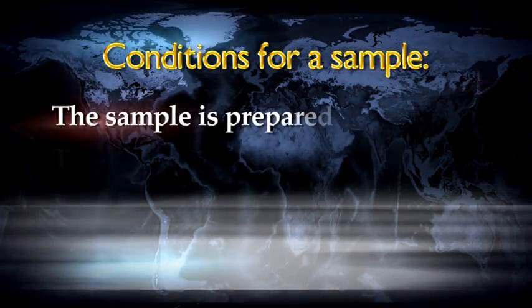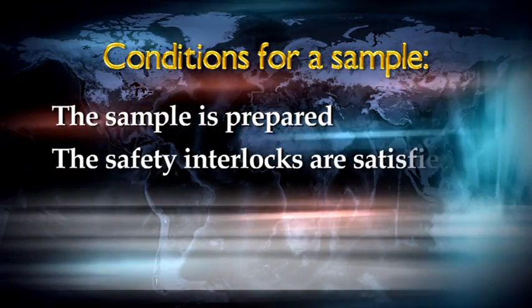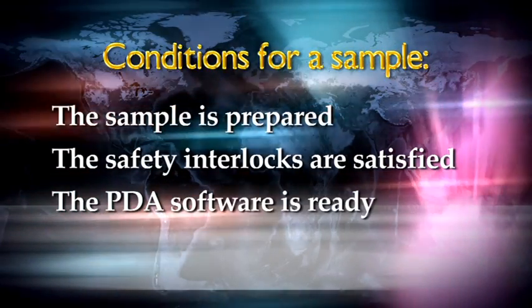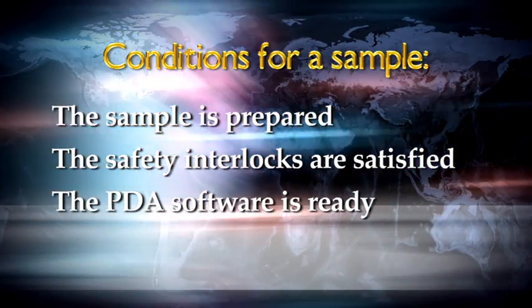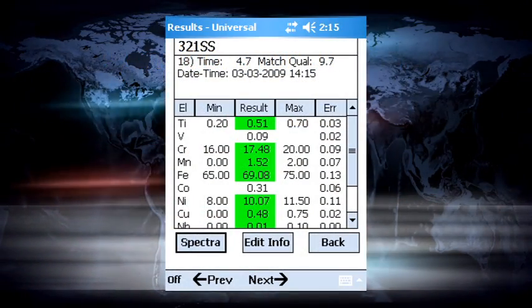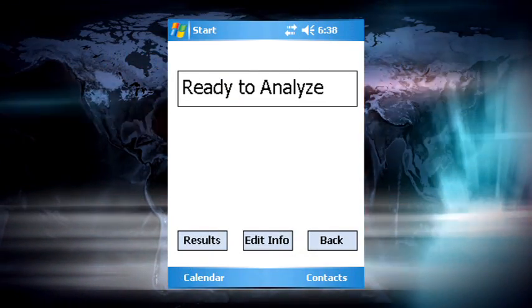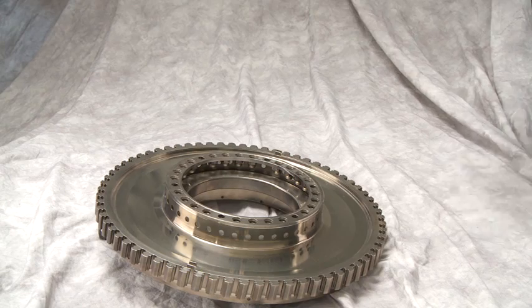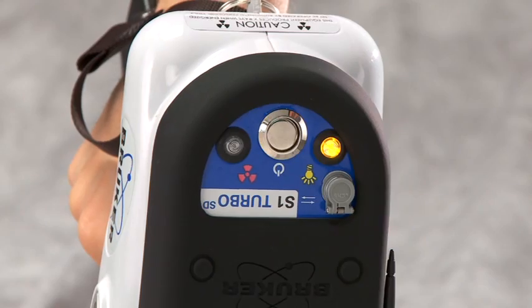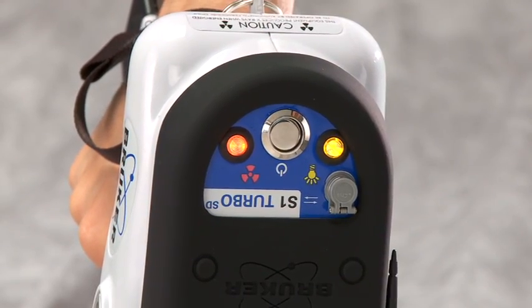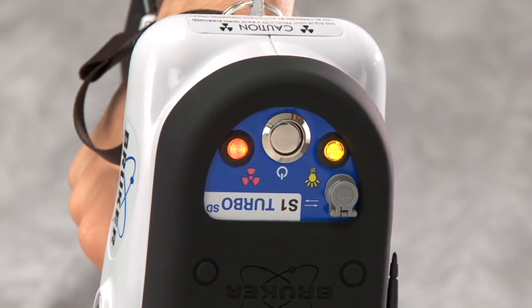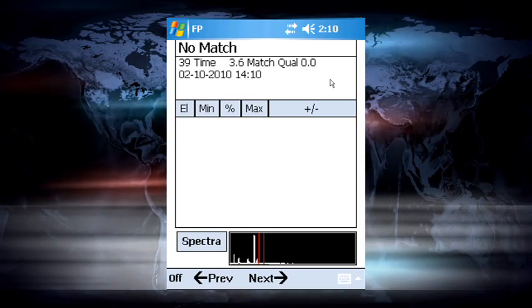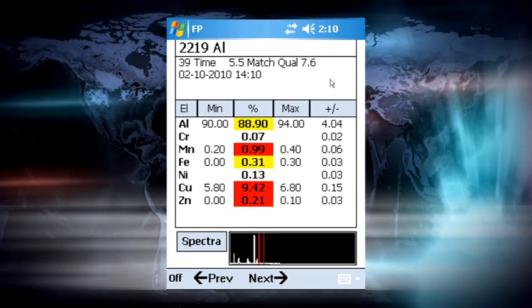Once the sample is prepared and the interlocks are satisfied, the final factor in starting the measurement is the state of the PDA software. There are two states where the analyzer can start an analysis: at the conclusion of the previous measurement, or at the Ready to Analyze screen shown here. If all of the conditions are met, then pulling the trigger on the instrument will start a measurement. This will be indicated by the red light on the control panel and data appearing on the screen.